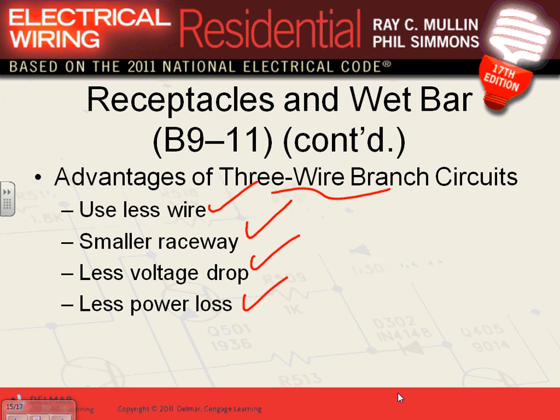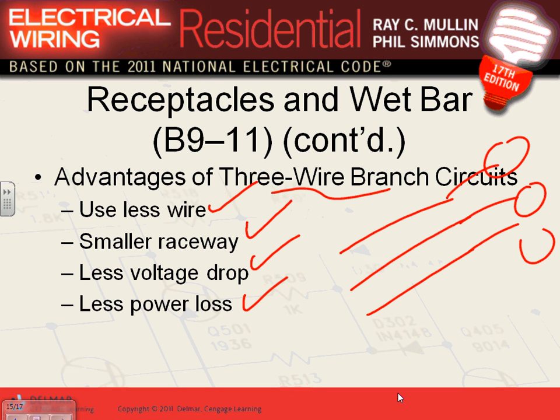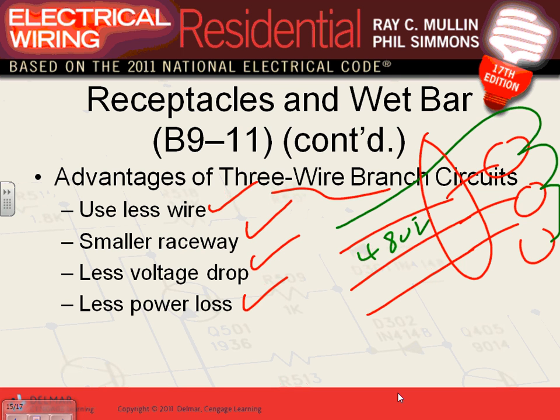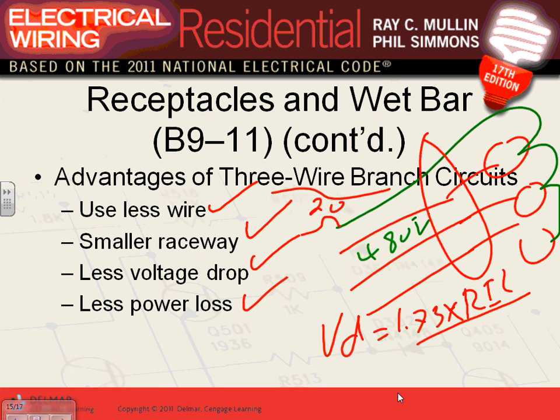Any questions, guys? Take this one. If you're using a multi-wire branch circuit here, and here's your light, and you're using a shared neutral, and this is a 480 volt system, look at the voltage drop in the whole system here. If you're doing lights on 20 amps, I'm going to do it very fast. Voltage drop equals 1.73 times R I L over 1,000. This becomes a 3-phase, right? Because this is light, but they share the neutral, they will be seen as a 3-phase, and you apply the 3-phase formula for it.